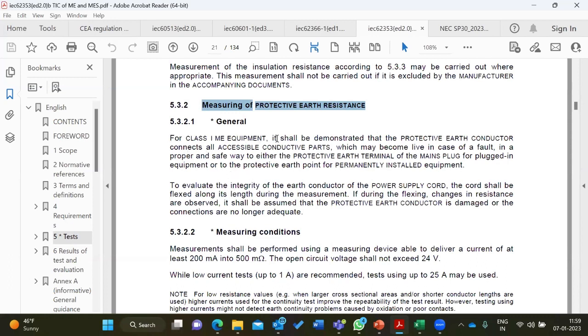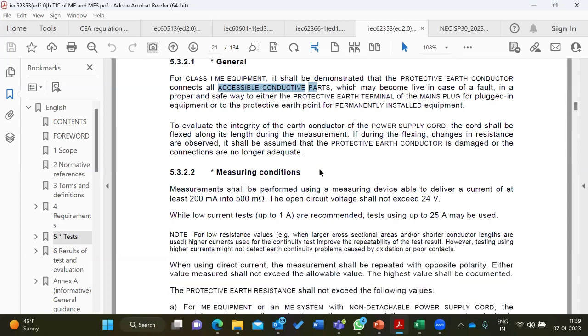Now, I will just read out for your information. For class 1 medical equipment, it shall be demonstrated that the protective earth conductor connects all accessible conductive parts. Very simple to understand. There is an earth terminal on the equipment, and this earth terminal must be connected to all exposed conductive parts of that particular machine. That means the body or different kinds of exposed parts. And after repair, before you connect it to service again, you are supposed to take a measurement of the continuity resistance. Continuity resistance means you should find out the connection is proper and strong.